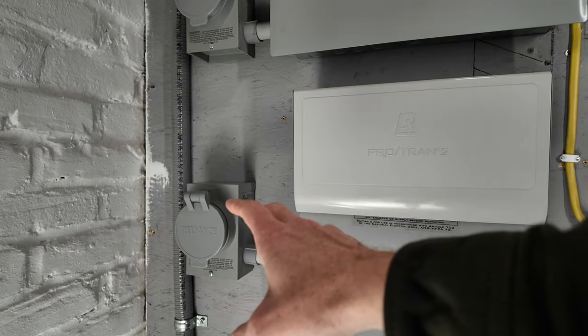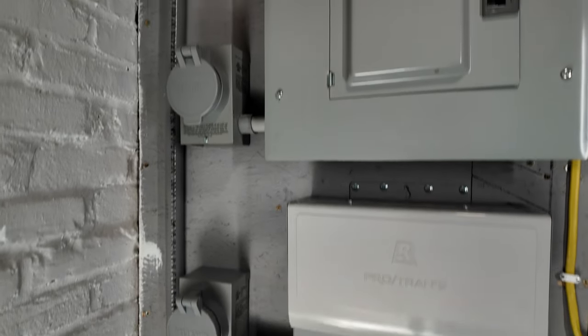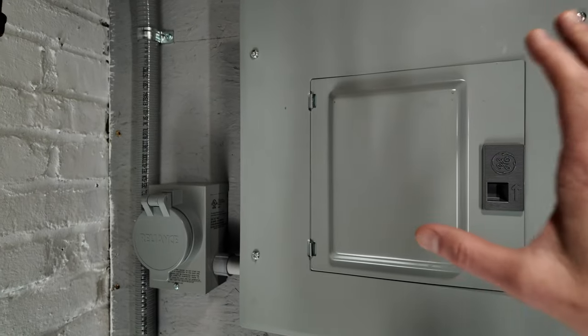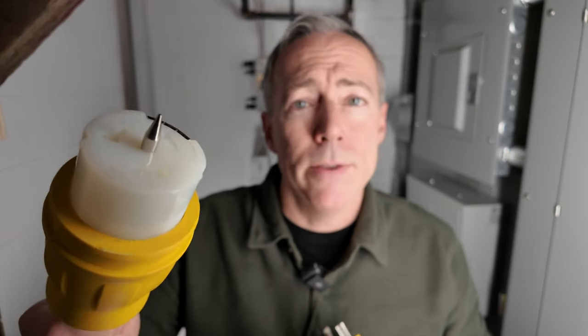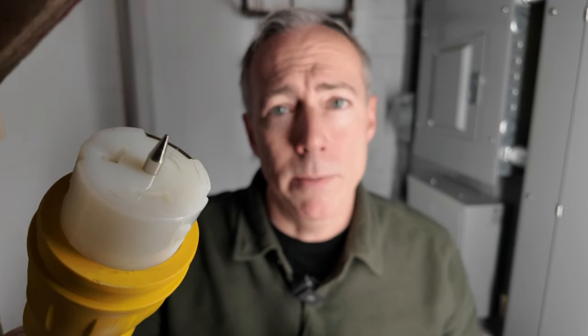There's a power inlet port for the transfer switch and a separate one up here for the sub panel. To connect these together, I need a special cable that has a 30 amp plug on one side that goes into the Ultra and a 50 amp plug on the other side that will go into my power inlet ports.